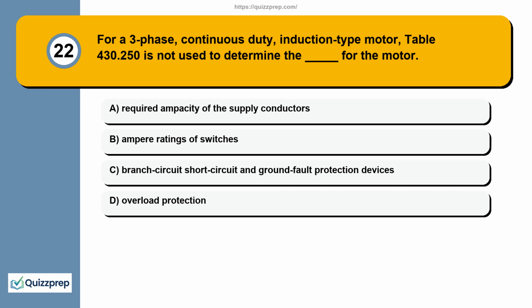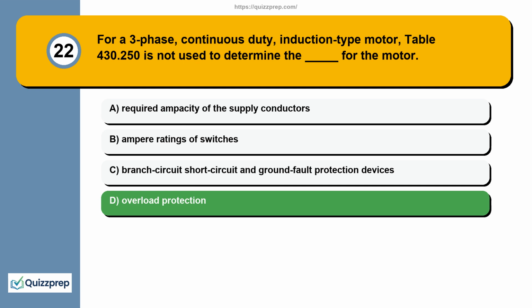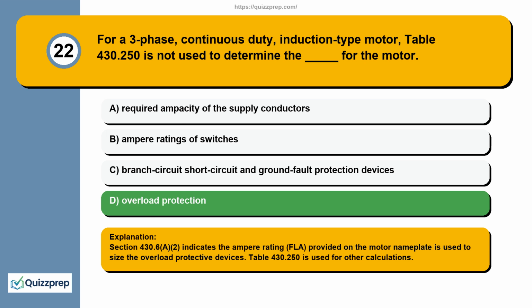Question 22. For a three-phase, continuous duty, induction type motor, Table 430.250 is not used to determine the: motor, required ampacity of the supply conductors, ampere ratings of switches, branch circuit short circuit and ground fault protection devices, overload protection. Section 430.6(A)(2) indicates the ampere rating, FLA, provided on the motor nameplate is used to size the overload protective devices. Table 430.250 is used for other calculations.